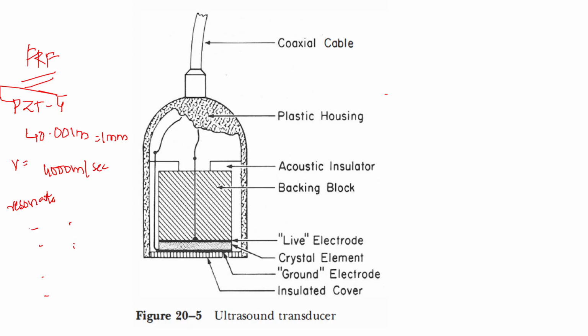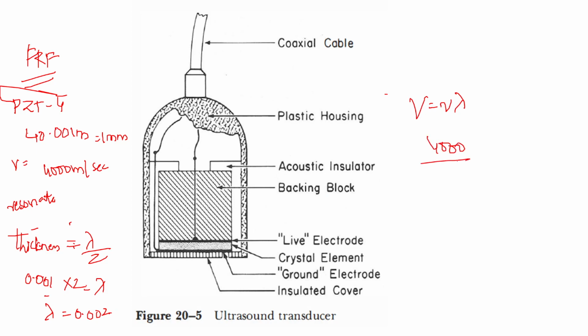So we have said that the thickness of the piezoelectric crystal should be half the wavelength. So thickness here is given as 0.001, into 2 is equal to wavelength. So wavelength is equal to 0.002. Okay. Now we know velocity is equal to nu lambda. Velocity is 4000 by 0.002 equal to nu. Nu is nothing but frequency. So from this we can calculate the frequency as almost 2 megahertz. So a 2 megahertz piezoelectric crystal is made at a thickness of 0.001 meters.